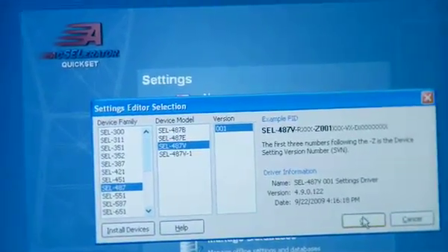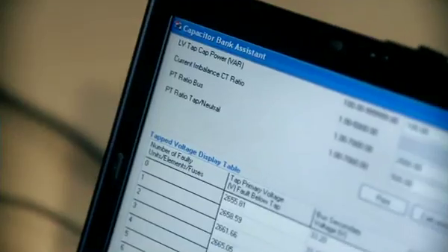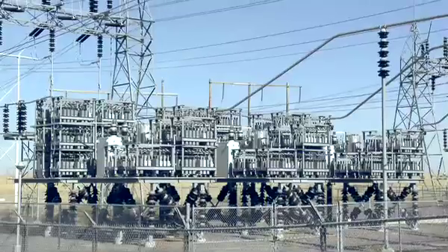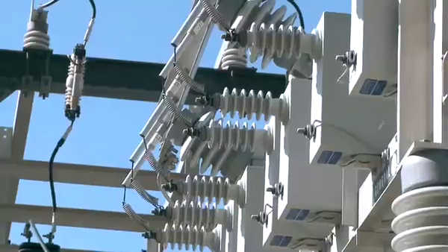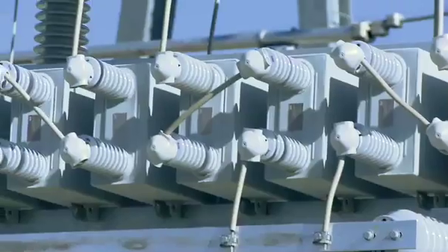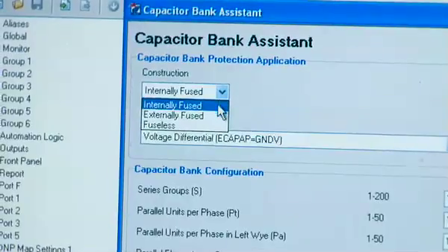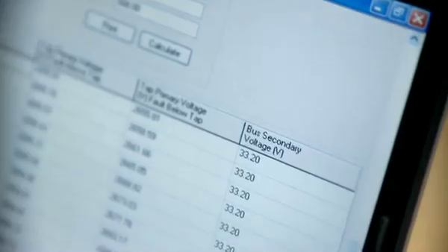The user-friendly capabilities through settings assistance provide the ability to configure the 487V relay for grounded or ungrounded capacitor bank applications, as well as single or dual parallel Y capacitor bank configurations. You enter the type of bank configuration and it will calculate the settings from there using the IEEE standard, so you don't actually have to look at the equation — it's already entered in there for you.